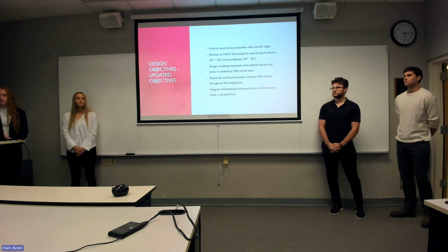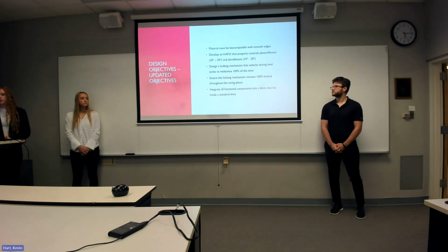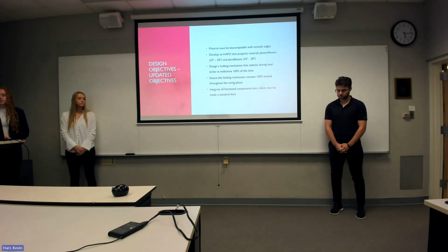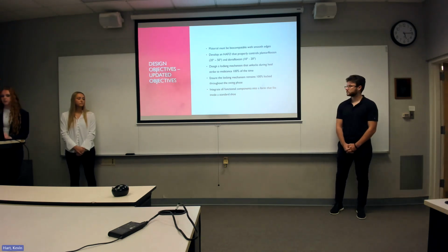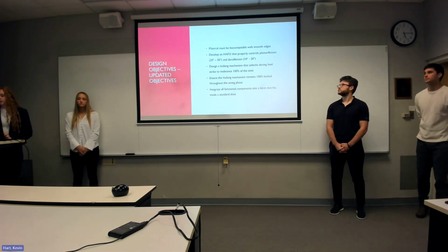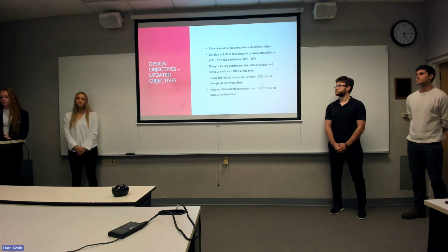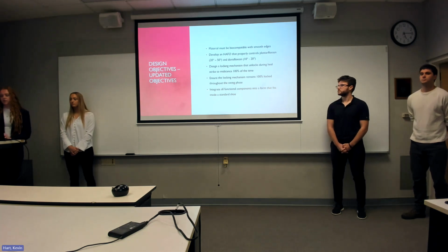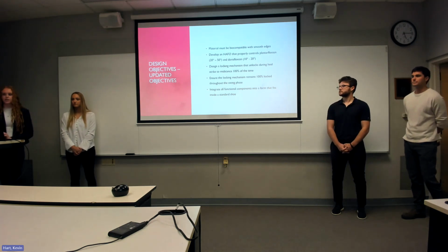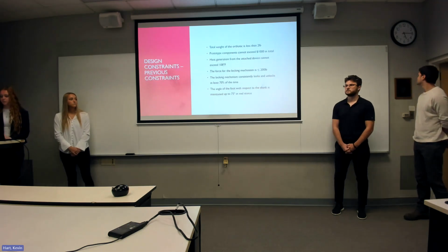We also separated the locking behavior into two clear requirements. The device must unlock during heel strike to mid stance so that the user can walk naturally. And it must stay fully locked during the swing phase to prevent that toe drag. Finally, we need to make sure that the HAFO can fit in a standard shoe as patients will be wearing this throughout the day. It needs to fit the shoe.